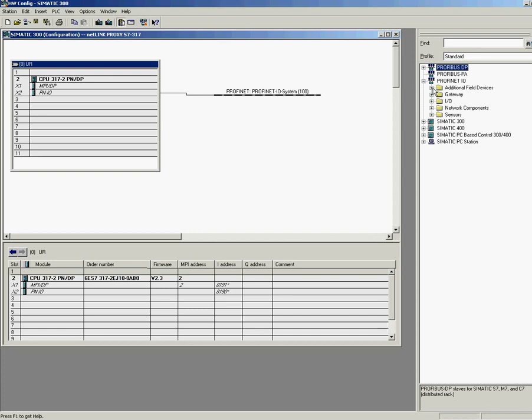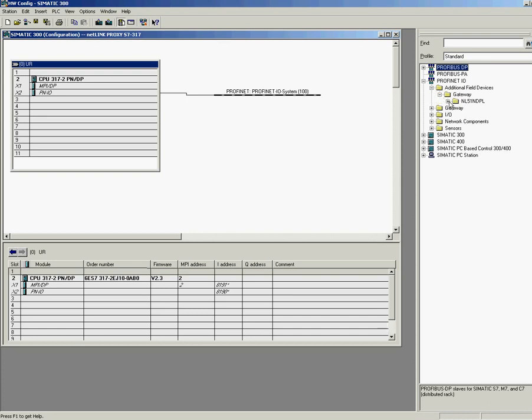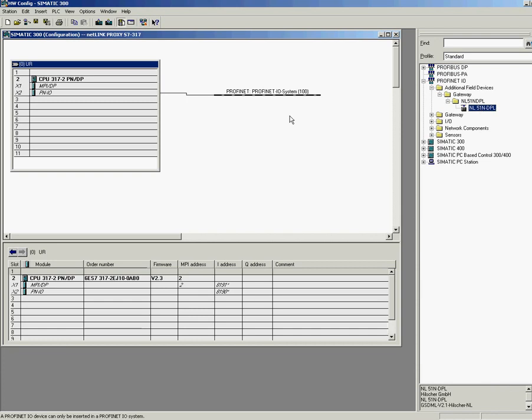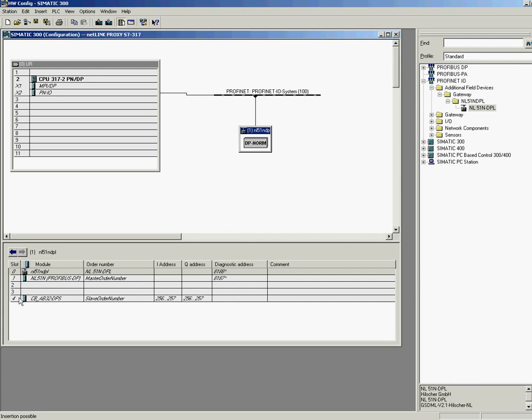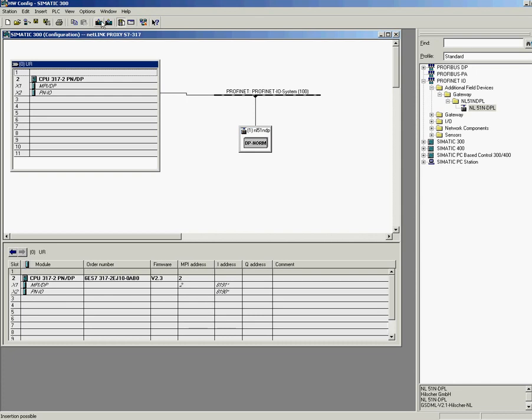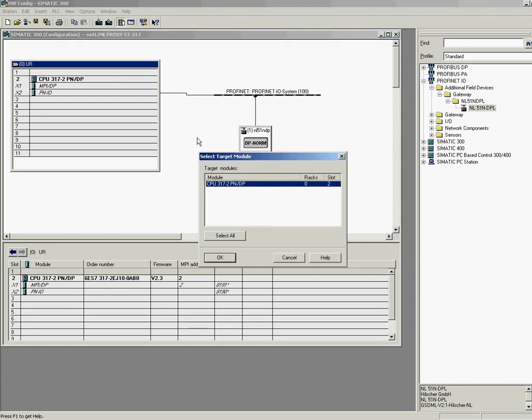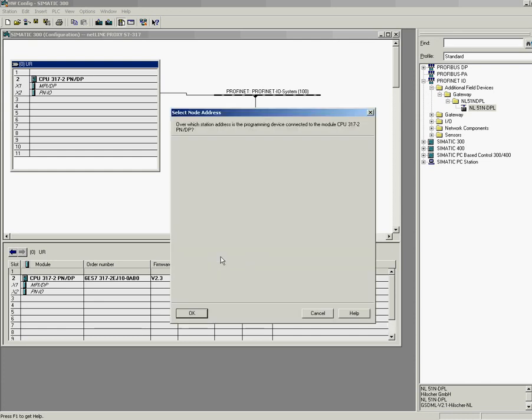Now look. While before my list of additional devices was empty, now you find here the Netlink that I drag and drop now to the empty bus line. You can look to the device's configuration when you click on it. You see three slots occupied. And here's the slave with the address 4 that is proxied from this Netlink. After importing now and placing the device, we can now make a download to the PLC.